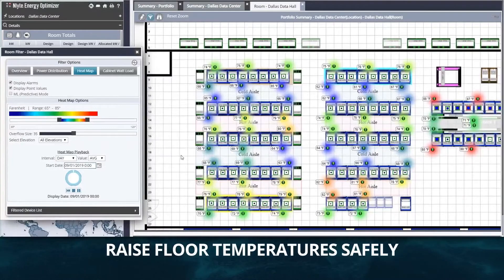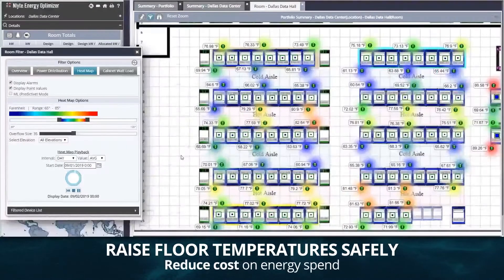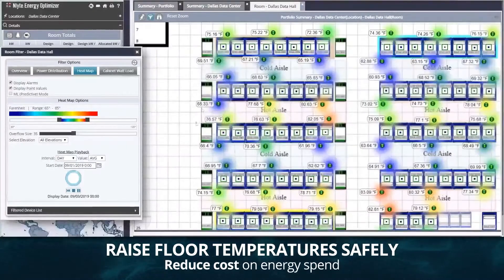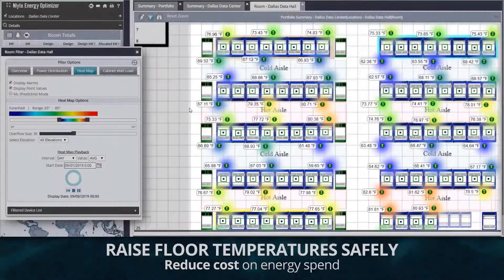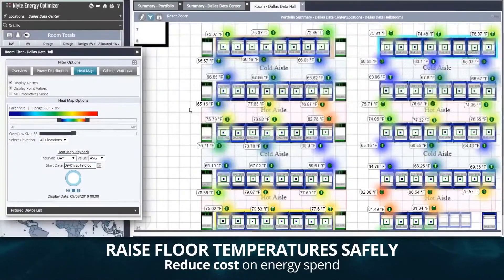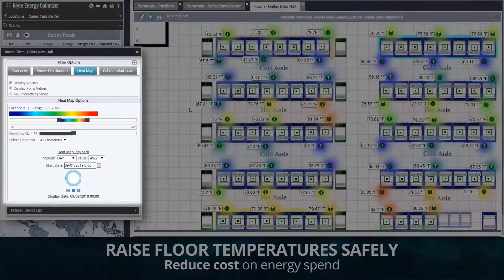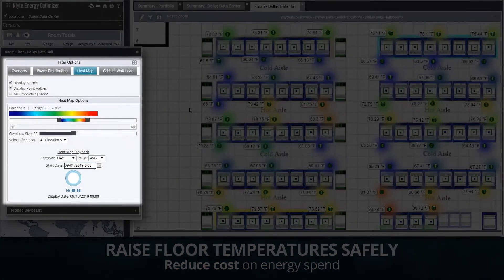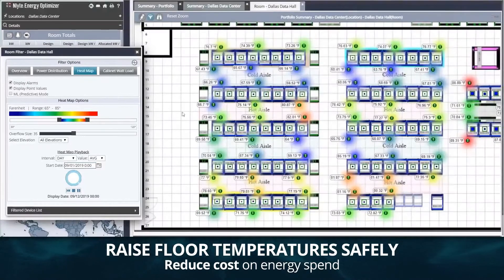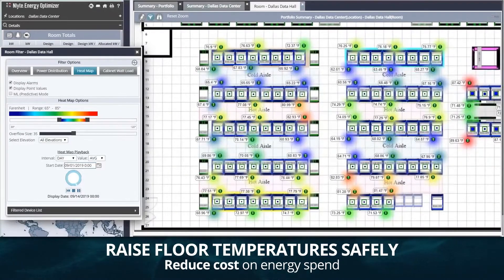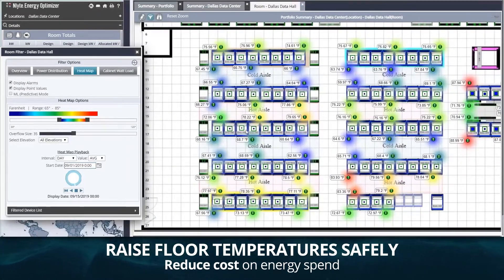Another use case helps reduce cost on energy spend by allowing you to raise data center temperatures safely. The monitoring of real-time and trending ambient temperatures at subfloor, top of rack, and ceiling lets you slowly raise the set points of the CRAC units, reducing power consumption and cost.